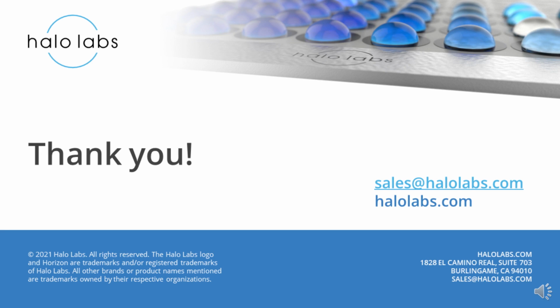Hello, everyone. That's a good question, and we get it often. The BMI technology is more sensitive than flow imaging methods. As I explained, we have a higher refractive index contrast, meaning that we can see particles that would be invisible for flow methods, including MFI and FlowCam, and therefore do a better job. In addition, this is a compendial method. So what that means is that there are actually counts established for membrane microscopy, while there aren't any for flow methods.